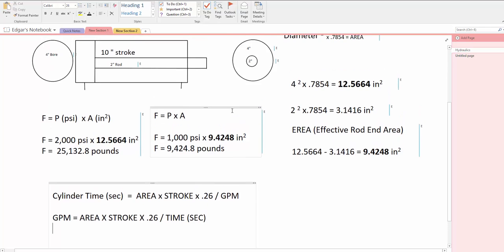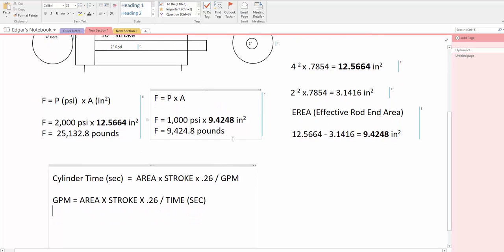After we have the areas, we can come out with the formula and we say cylinder time in seconds equals area times stroke times .26 divided by GPM. You can also change the formula around and say GPM equals area times stroke times .26 divided by time.